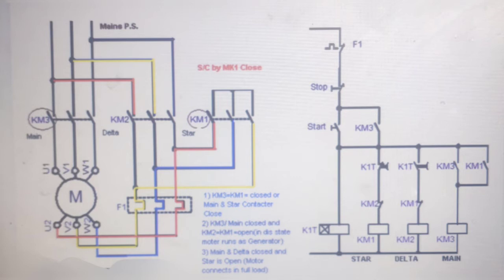In operation, the main contactor KM3 and the star contactor KM1 are closed initially, and then after a period of time the star contactor is opened and delta contactor is closed. The control of the contactor is by the timer.